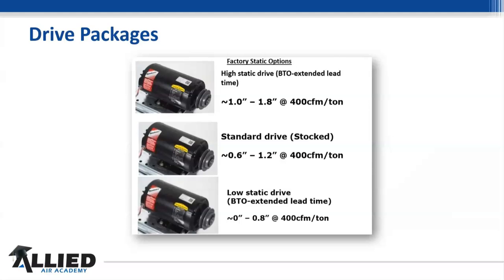I'll pull this up. This is kind of the rule of thumb for factory options, the static pressures of what standard, high static, and low static drives are going to be. It's really important to understand where these static pressures fall and what you're doing, because if you're doing a plan and spec, that's all fine and good. You can get the unit, put it on Pro Design, and get everything built around it. But if you're doing a replacement, understand that if you've got a wide open return, a standard drive may not work for you. You may have to go down to a lower static drive or make some changes on your sheaves and pulleys.